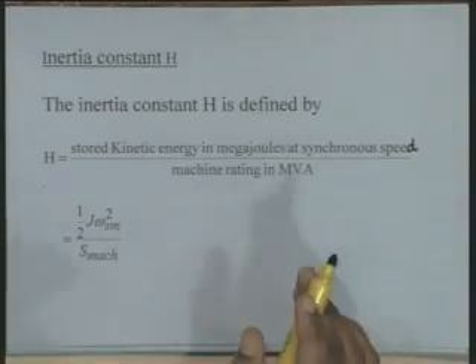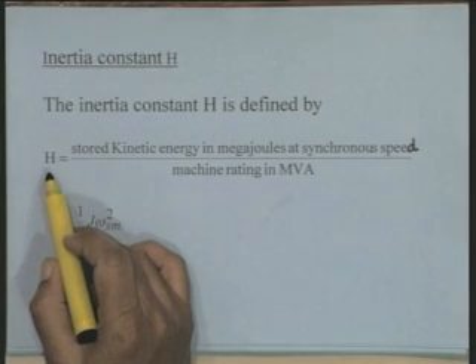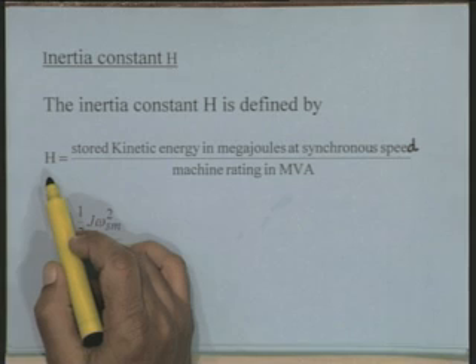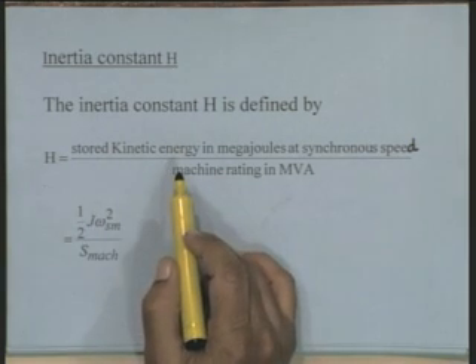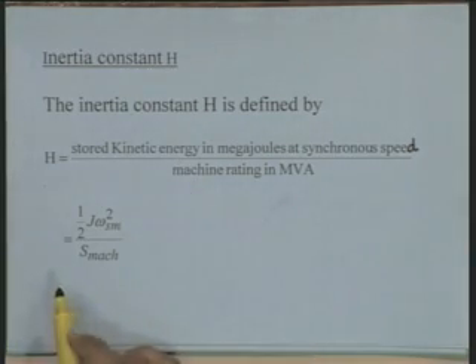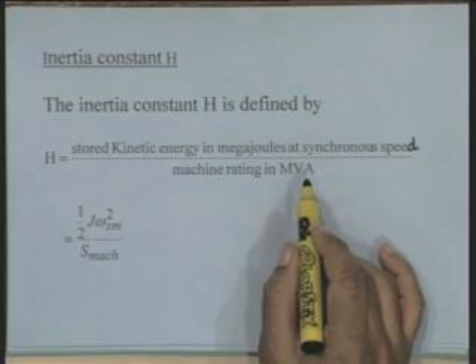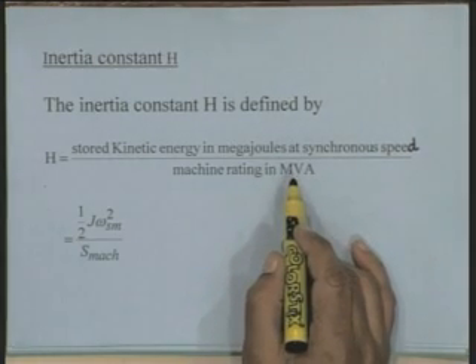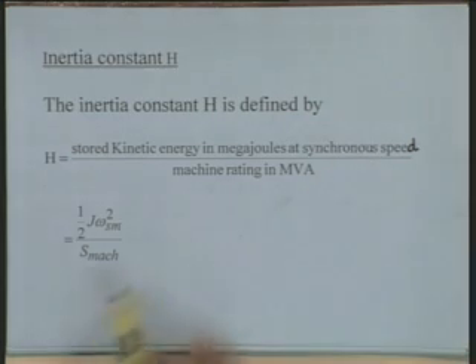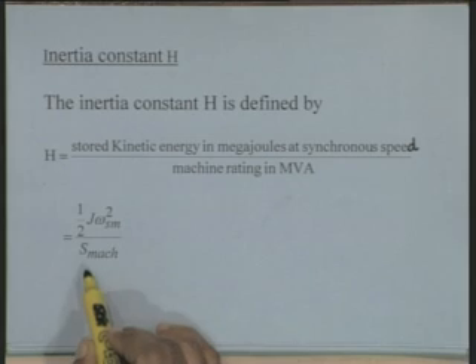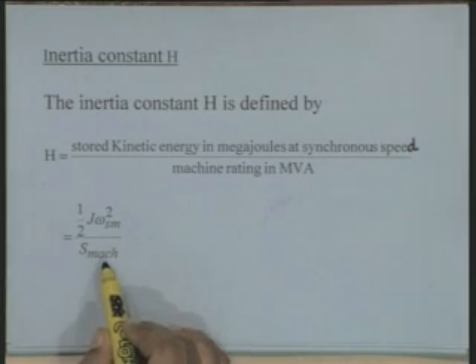For any synchronous machine, when the rotor is rotating at synchronous speed, we can find the kinetic energy stored in the rotor, and divide this by the machine rating. If kinetic energy is in megajoules and machine rating in MVA, the unit becomes megajoules per MVA. We can also represent it as kilojoules per KVA. But since machine ratings are normally in MVA, we prefer energy in megajoules and rating in MVA. Therefore, this can be written as 1 by 2 J omega Sm square upon the machine rating S Mach.